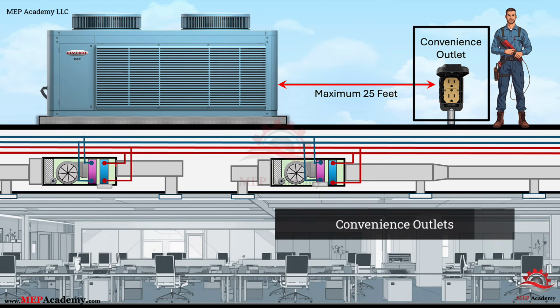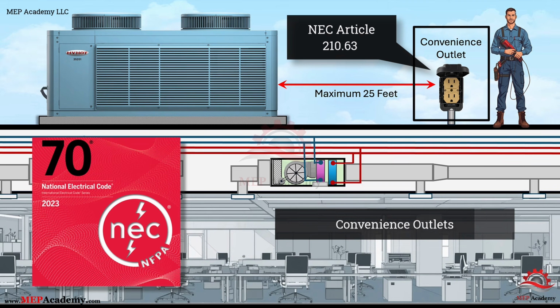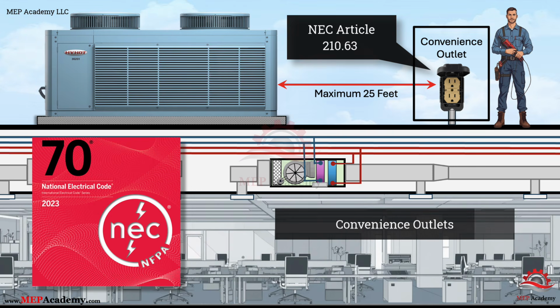Maintenance personnel require power to safely service equipment, and this requirement is addressed in the National Electrical Code. NEC Article 210.63 requires a 125-volt, single-phase, 15 or 20-ampere receptacle outlet to be installed at or near heating, air conditioning, and refrigeration equipment for servicing purposes. These outlets must be located within 25 feet of the equipment. Despite this requirement, service receptacles are frequently missing from electrical plans or assumed to be included without being clearly shown. The problem is commonly discovered during inspection or turnover when a required outlet is not present. Late installation can result in exposed conduit runs, additional roof penetrations, or coordination conflicts with finished work. Estimators should verify whether service outlets are included and clearly identify responsibility for providing and installing them.